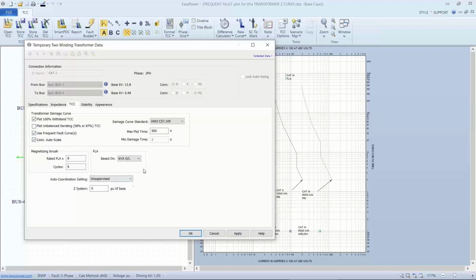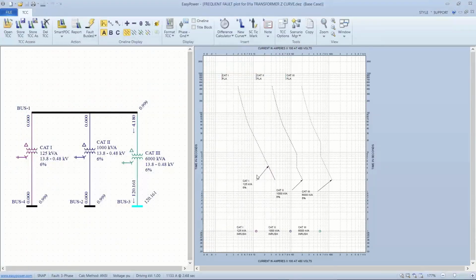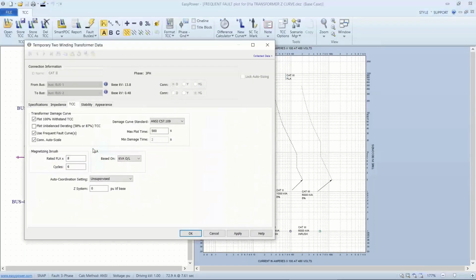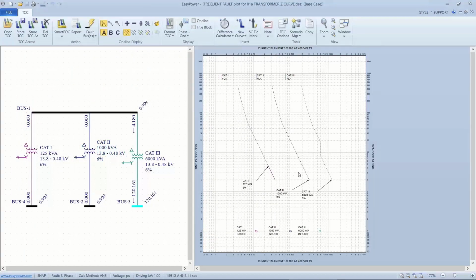So if I go back and look at the setup, we're asking for a frequent fault curve in the smaller transformer, but because ANSI C57.109 doesn't have one, there's no jog in this plot. Whereas when we go to Cat 2, we're asking for a frequent damage curve, frequent fault curve. If I uncheck that box, watch what happens to the plot, this middle one. So what this means is this is the 100% damage curve.